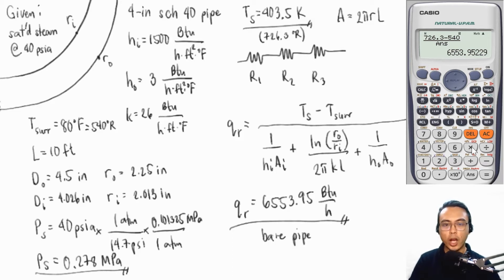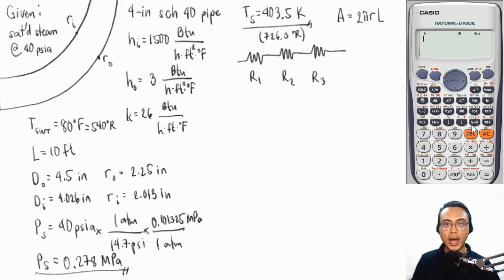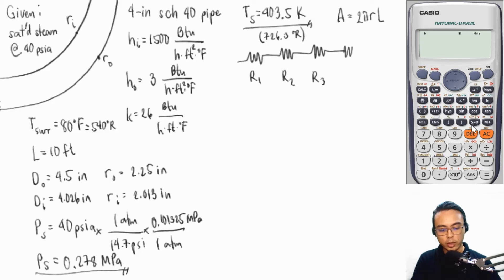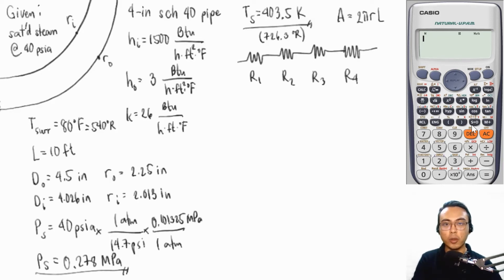For the next part, we want to see what happens to the rate of heat transfer if we place 2 millimeters of rubber insulation on the pipe. We are adding another conductive resistance, making our total resistances four. R1 and R4 are due to convection on the inside and outside respectively, R2 represents the resistance of the pipe wall, and R3 represents the resistance of the insulating material.